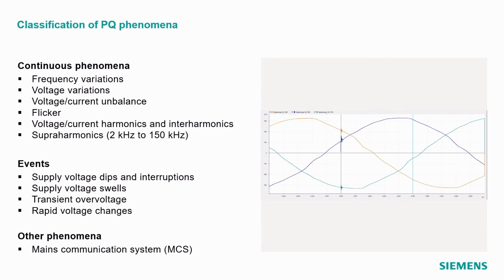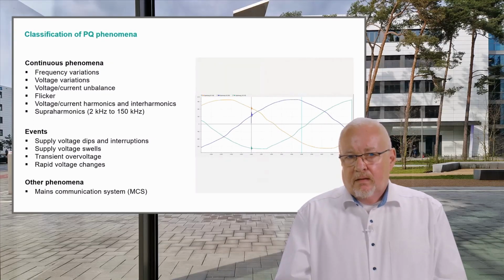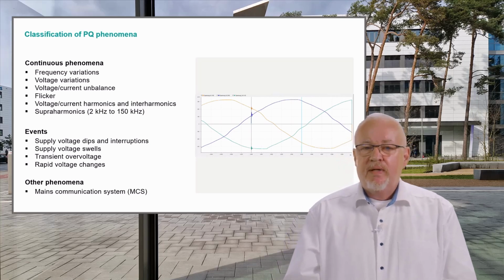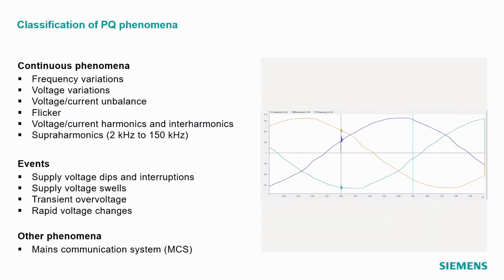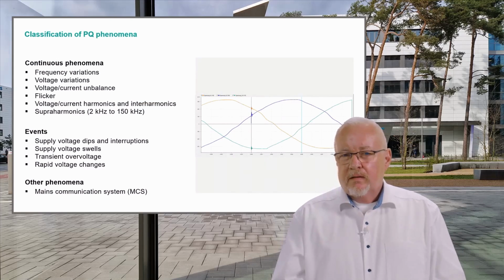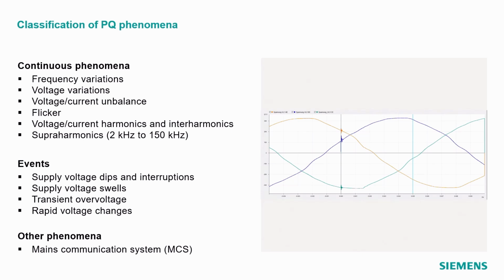And there's another type which is inserted in the power system, so-called mains communication systems. These are control signals which are inserted to control equipment in the power system by voltage pulse patterns. I give you a short explanation with the picture on the right side. You see here that the waveform isn't a sine wave. There are some disturbances visible, caused by low frequency phenomena like harmonics, which disturb the sine waveform, and there are additional spikes on the curves you see here, which are caused by very high switching frequencies and are measured as so-called supraharmonics.